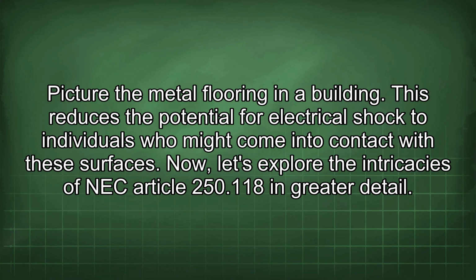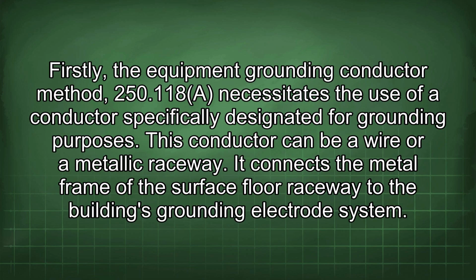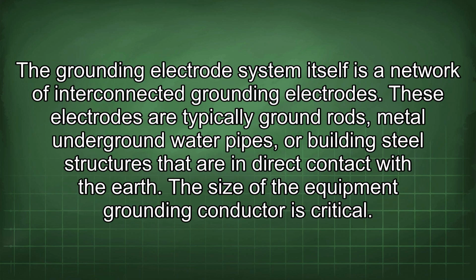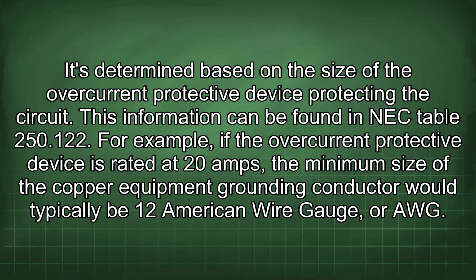Now, let's explore the intricacies of NEC Article 250.118 in greater detail. Firstly, the equipment grounding conductor method. 250.118 necessitates the use of a conductor specifically designated for grounding purposes. This conductor can be a wire or a metallic raceway. It connects the metal frame of the surface floor raceway to the building's grounding electrode system. The grounding electrode system itself is a network of interconnected grounding electrodes. These electrodes are typically ground rods, metal underground water pipes, or building steel structures that are in direct contact with the earth. The size of the equipment grounding conductor is critical. It's determined based on the size of the overcurrent protective device protecting the circuit. This information can be found in NEC Table 250.122. For example, if the overcurrent protective device is rated at 20 amps, the minimum size of the copper equipment grounding conductor would typically be 12 American wire gauge, or AWG.